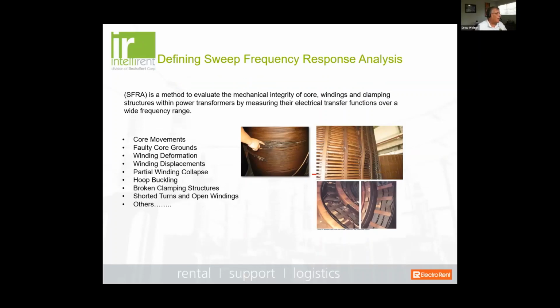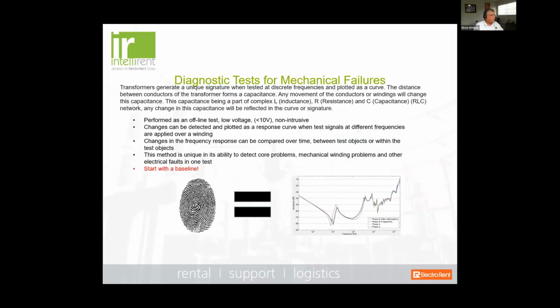Okay, so an SFRA test is there to evaluate the mechanical integrity of the core, the windings, and clamping structures within power transformers. Now, what can be the result of a high through fault? Well, you can have core movements, faulty core grounds, winding deformation, winding displacements, partial winding collapse, and hoop buckling, and you'll see this indicated in some of the illustrations here. These are transformers that have been damaged, showing mechanical failure in the windings. Now, basically, transformers generate a signature. This is the whole purpose of SFRA.